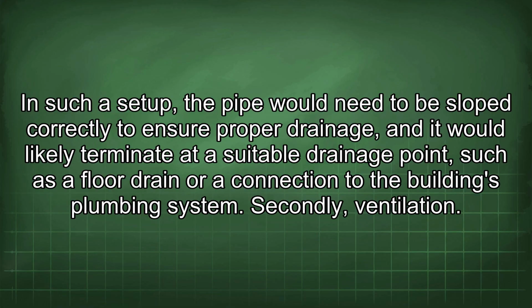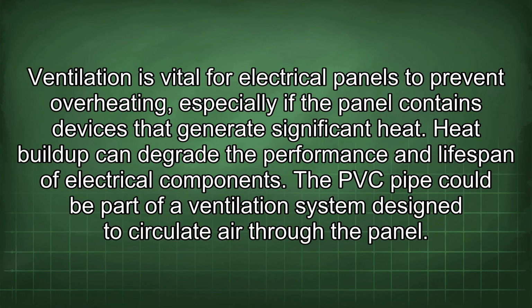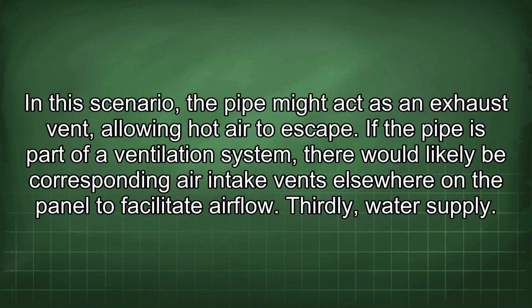Secondly, ventilation. Ventilation is vital for electrical panels to prevent overheating, especially if the panel contains devices that generate significant heat. Heat buildup can degrade the performance and lifespan of electrical components. The PVC pipe could be part of a ventilation system designed to circulate air through the panel. In this scenario, the pipe might act as an exhaust vent, allowing hot air to escape. If the pipe is part of a ventilation system, there would likely be corresponding air intake vents elsewhere on the panel to facilitate airflow. Thirdly, water supply.